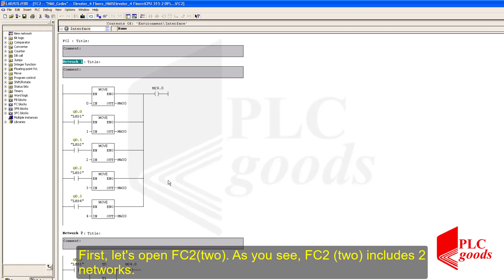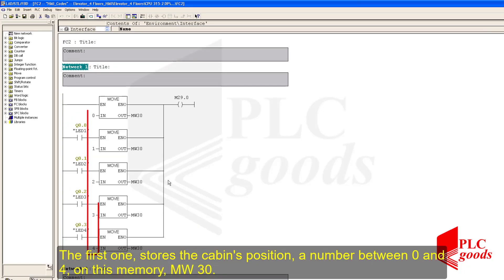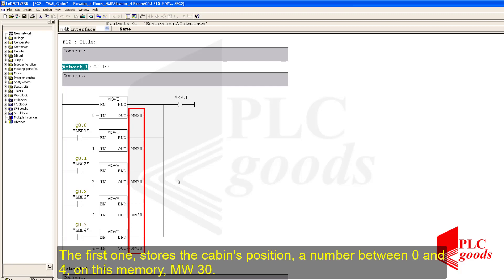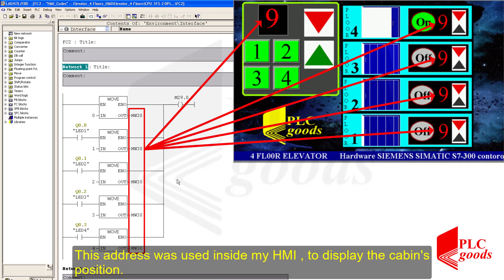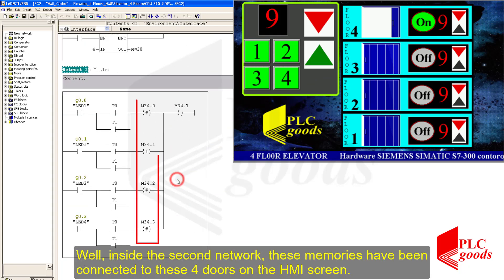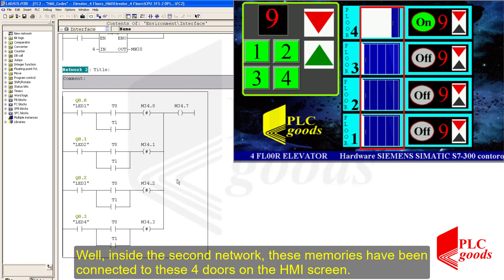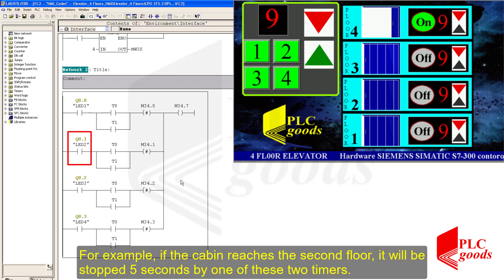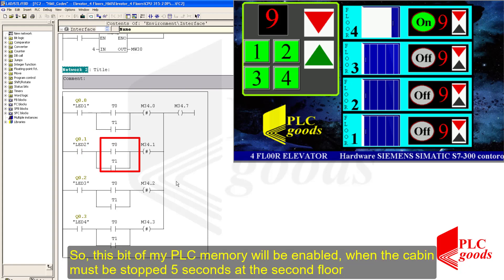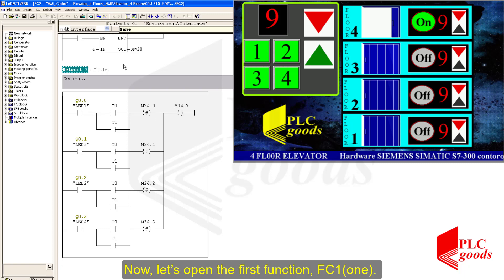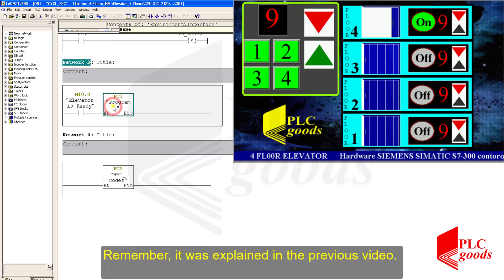The second function includes two networks. The first one stores the cabin's position — which is a number between 0 and 4 — on memory MW30. This address was used inside my HMI to display the cabin's position. Inside the second network, these memories have been connected to these four doors on the HMI screen. For example, if the cabin reached the second floor, it will be stopped five seconds by one of these two timers, so this bit of PLC memory will be enabled when the cabin must be stopped five seconds at the second floor. Now let's open the first function FC1.